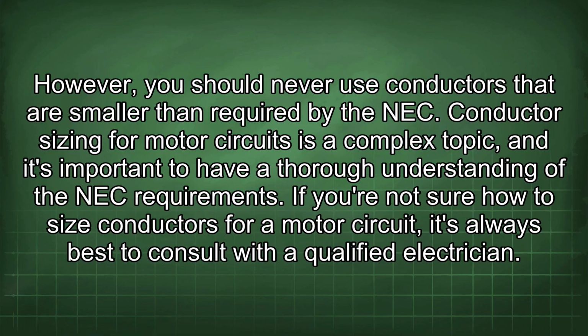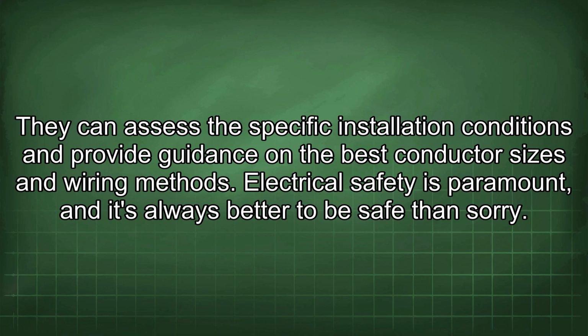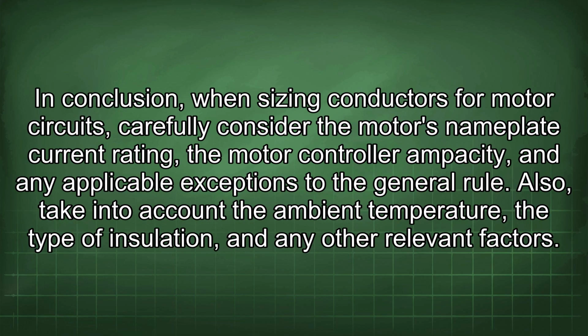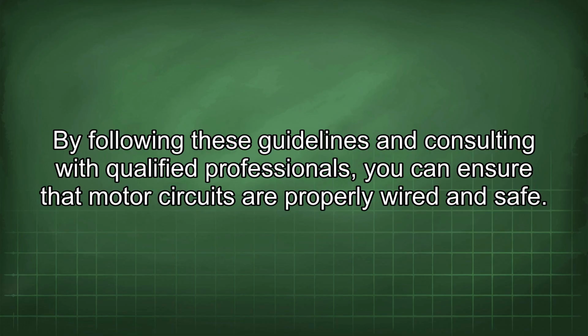Conductor sizing for motor circuits is a complex topic, and it's important to have a thorough understanding of the NEC requirements. If you're not sure how to size conductors for a motor circuit, it's always best to consult with a qualified electrician. They can assess the specific installation conditions and provide guidance on the best conductor sizes and wiring methods. Electrical safety is paramount, and it's always better to be safe than sorry. In conclusion, when sizing conductors for motor circuits, carefully consider the motor's nameplate current rating, the motor controller ampacity, and any applicable exceptions to the general rule. Also, take into account the ambient temperature, the type of insulation, and any other relevant factors. By following these guidelines and consulting with qualified professionals, you can ensure that motor circuits are properly wired and safe.